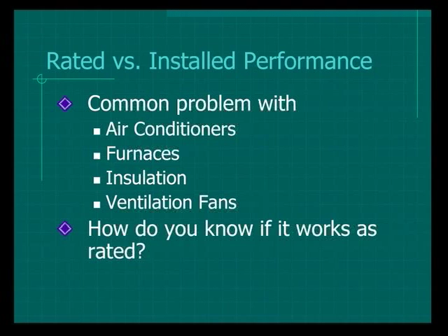Let's just talk about one, an air conditioner. We see 11-SEER air conditioners all the time. We'll test it, and they come out running at about 7. What's going on here? And even below that, they're running at 7 and delivering about 4 energy ratio, ER, which is part of that SEER, of cooling. That other 3 is going to dehumidification. In Colorado, we don't need much dehumidification. There are a few days of the summer that we do, but most of the time we don't. So my 11 is actually delivering 4 of cooling.